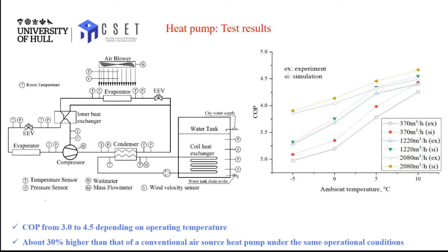We can say that if we increase the ambient temperature and ventilation flow rate, the COP of the heat pump will increase. For our prototype, its COP will be in the range of 3 to 4.5, depending on its operational temperature. Compared to a traditional air source heat pump, our heat pump achieved 30% higher COP at the same operational condition.